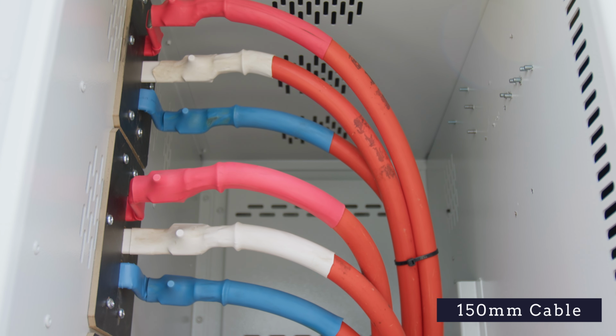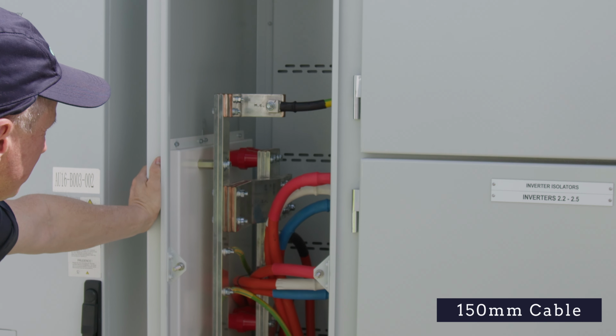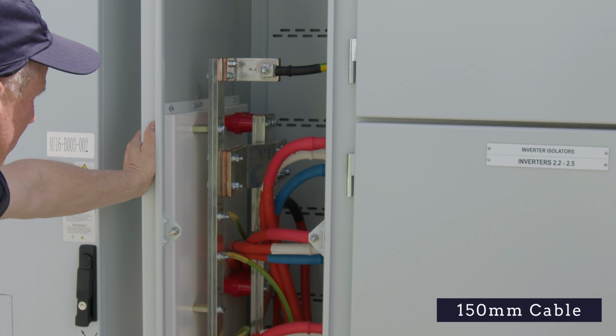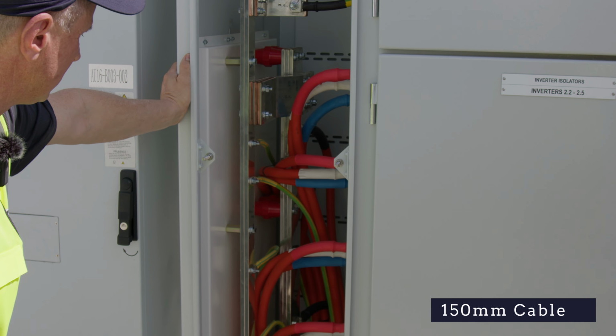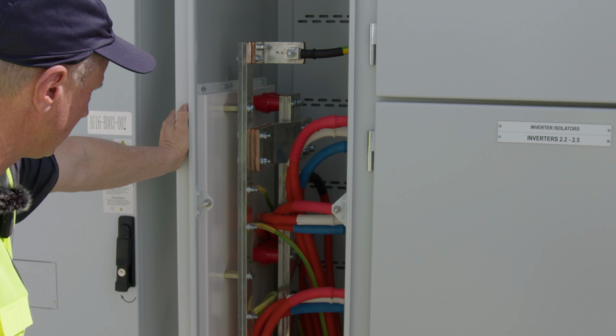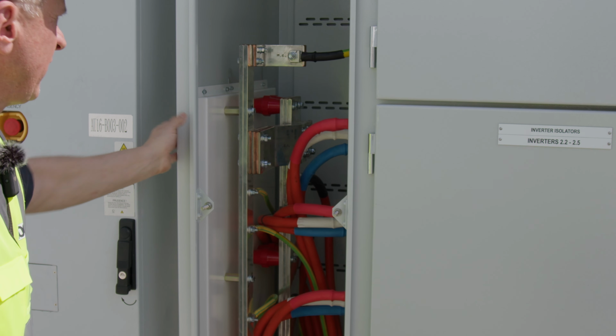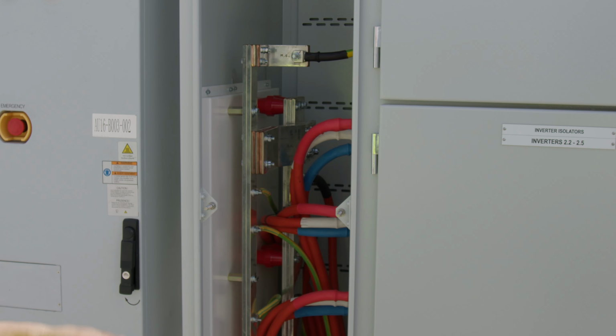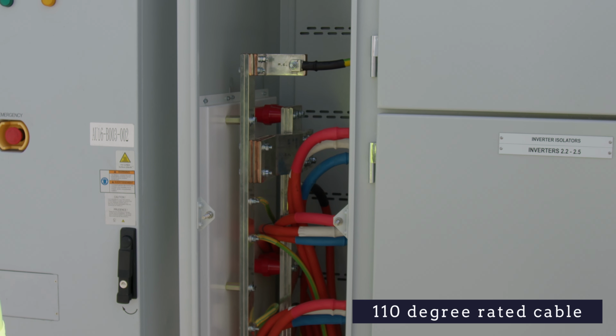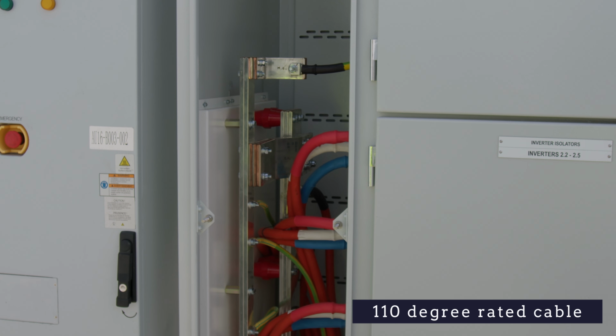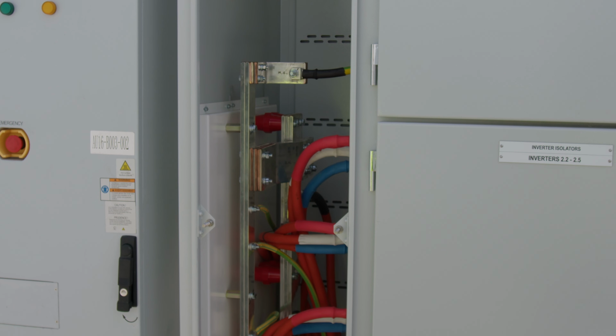So those cables there are 150 millimeter cable. They will supply 4 of the inverters on site. And the MEN link is inside this cabinet with the main earth connection. And obviously this is XLPE cable, because that's what we use. This is 110 degree rated. It's all fire rated to get that little bit of extra rather than going up cable size.